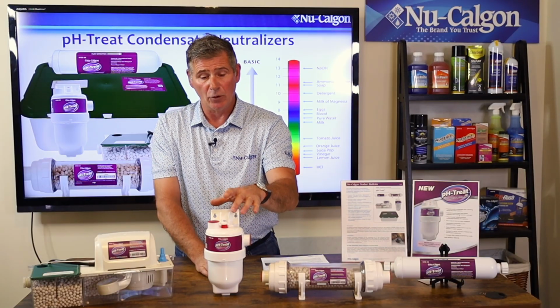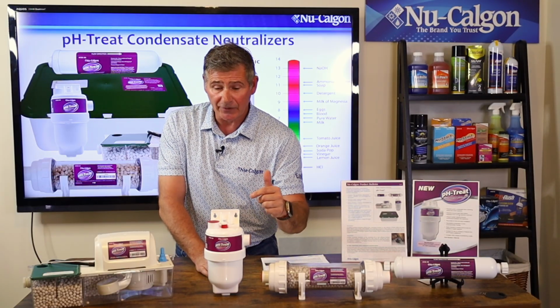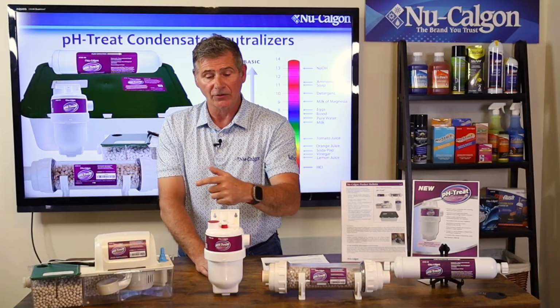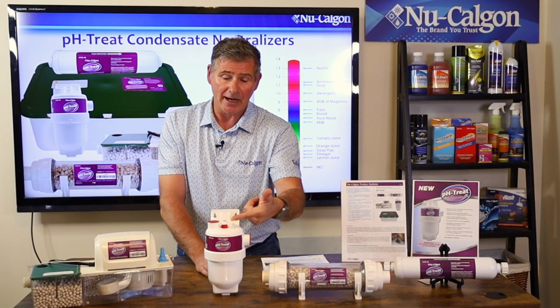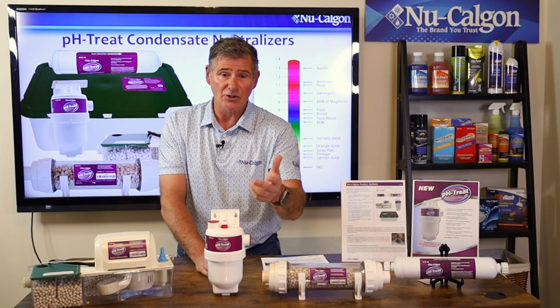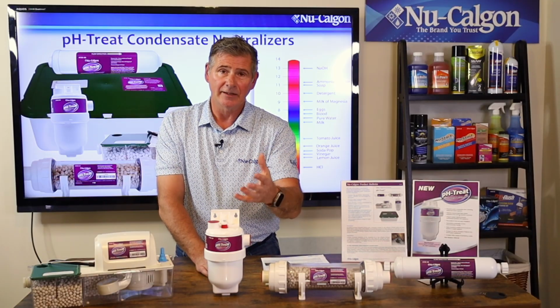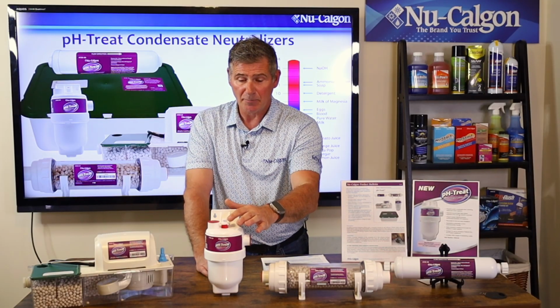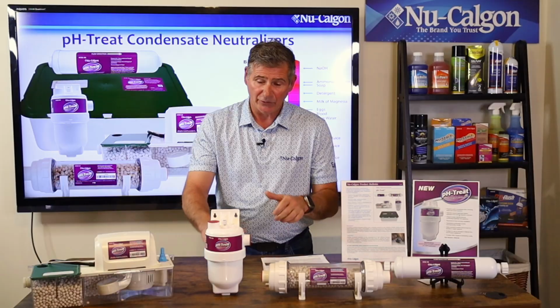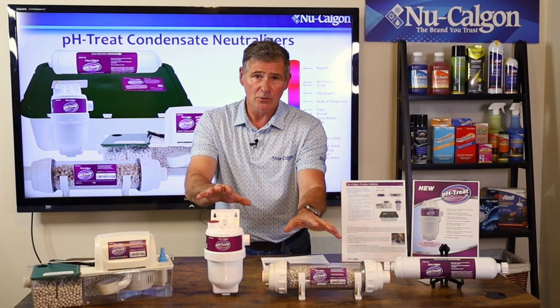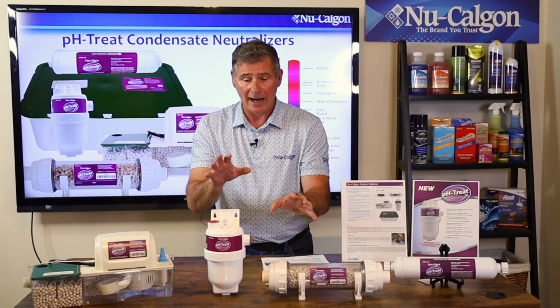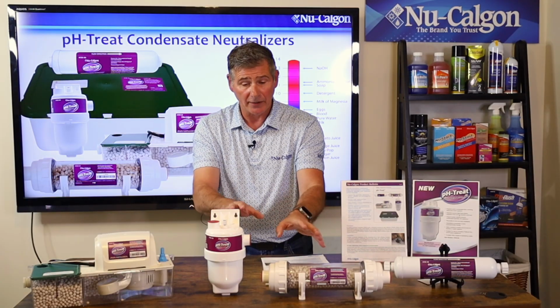Now, there is a backflow preventer in this, so we don't get that acidic water coming back up into the system. It's going to allow it to continue to drain, but at least it's going to let you know that there's an issue that needs to be addressed. More than likely, the media needs to be replaced, and then you can just pop that back down and you're off and running. So again, 400,000 BTUs, about 1.6 gallons per hour worth of condensate flow for either one of these.